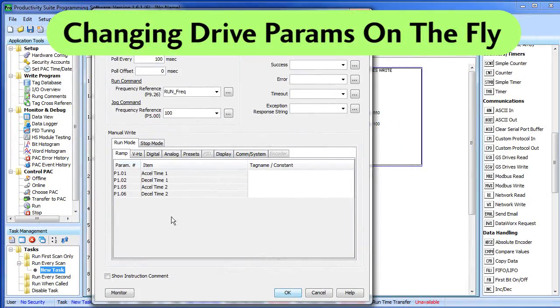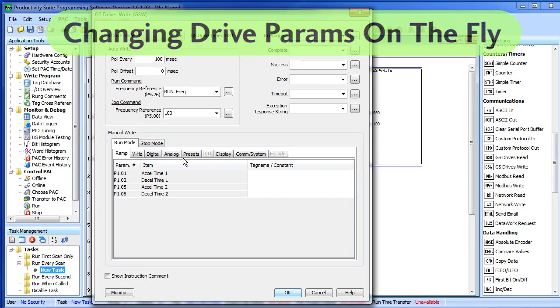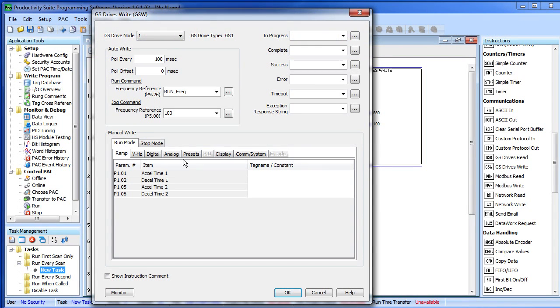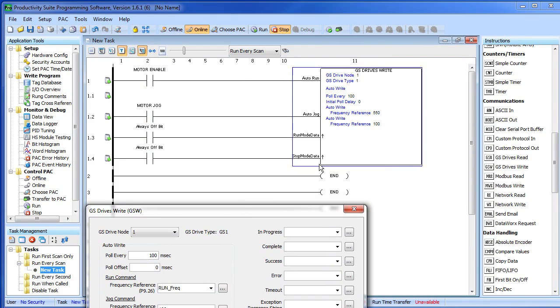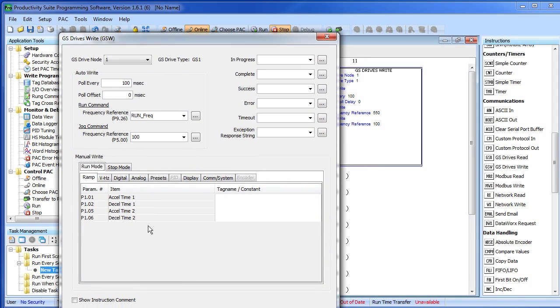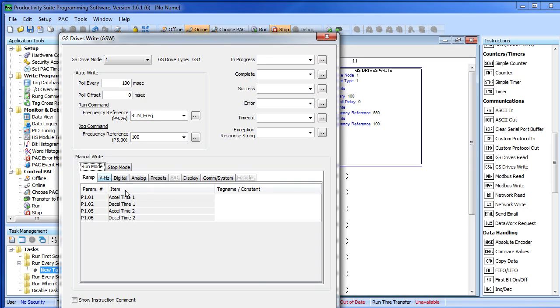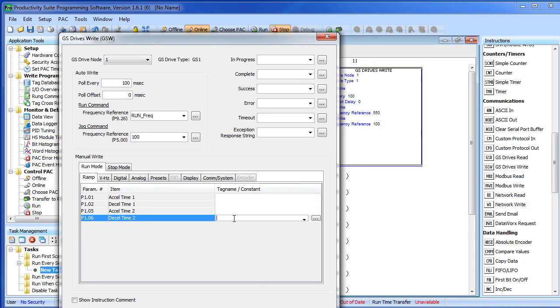These mode tables that you see in the GS read and GS write instructions give you a convenient place to change the GS drive parameters on the fly. If you enable run mode data, then any parameter that is defined anywhere on this run mode table with either a tag or a constant over here will be written to the drive. Parameters that are not defined will not be written.